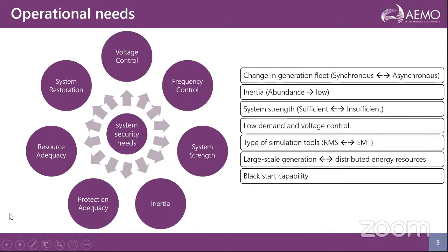System strength as a concept is an inherent characteristic of the grid, and it's related to the proximity to and amount of synchronous machines online. On the right side of this slide, you can see a diagram that conceptually tries to explain system strength. When a system has a very low amount of IBR, that is inverter-based resources, and the location of IBR is relatively close to the synchronous machines, it's called a high system strength scenario, and is shown by number 1 in the figure. Now, even with a low amount of IBR, if their location is far from synchronous machines, it can be categorized as a low system strength scenario, which would be more prone to instabilities. And this is shown by number 2 in the figure.